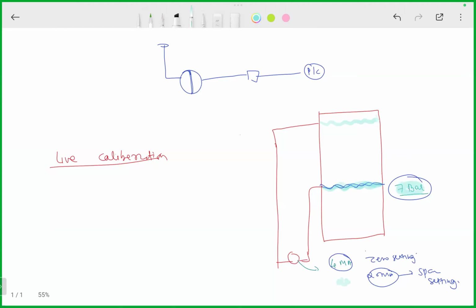Try to maintain it as close to the same value as possible, because this is your practical adjustment of the DP transmitter. What is your working pressure, sir? It is 7 bar. But what you are interested in is low level. So bring the water level to low level. Pressure can be slightly up or down. Acceptable, not an issue. Understood?